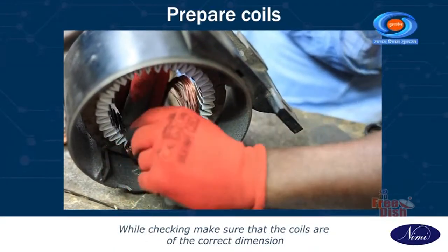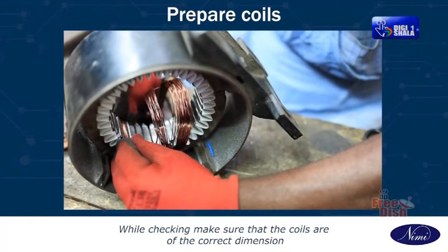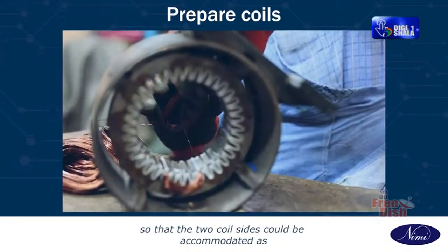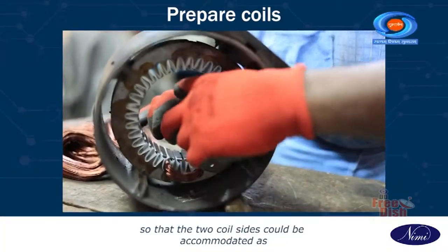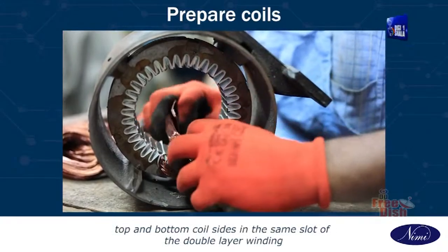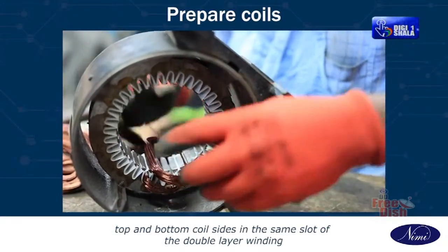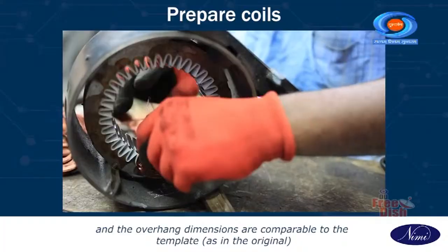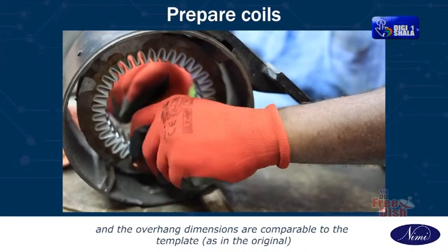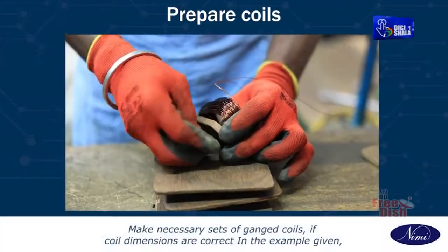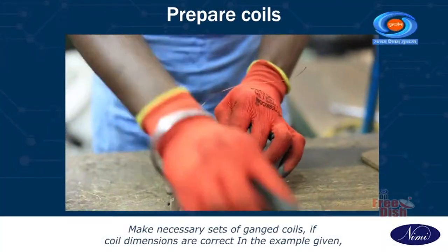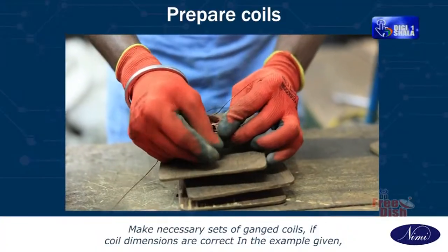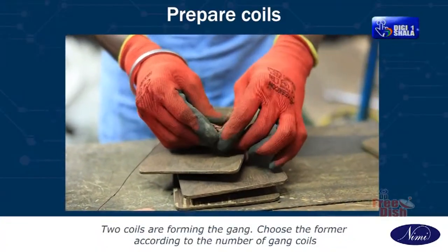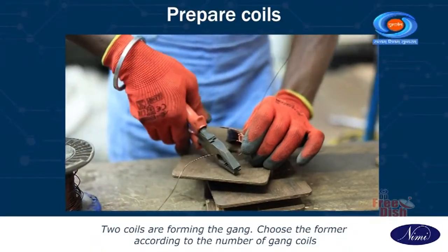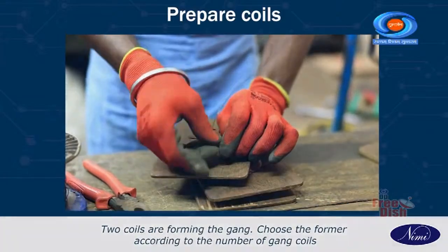While checking, make sure that the coils are of the correct dimension so that the two coil sides can be accommodated as top and bottom coil sides in the same slot of the double layer winding, and the overhang dimensions are comparable to the template as in the original. Make necessary sets of ganged coils if coil dimensions are correct. In the example given, two coils are forming the gang. Choose the former according to the number of gang coils.